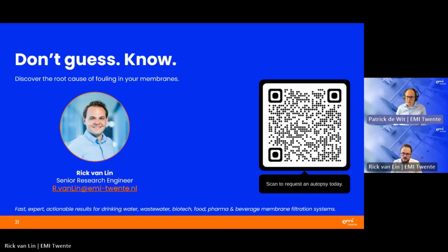Yeah, I think also you're sampling the element at different locations, right? Yeah. So looking at the entire length of the membrane, so the front parts, middle parts, concentrate parts, is pretty important to see if this changes over the module and if that's in line with the rest of the membrane. Also, let's say outer layer and inner layer of the envelopes.